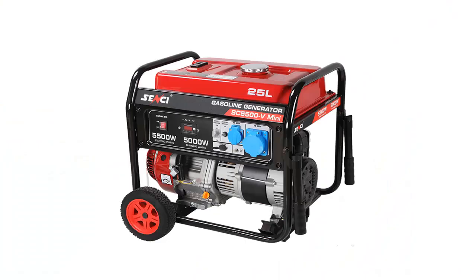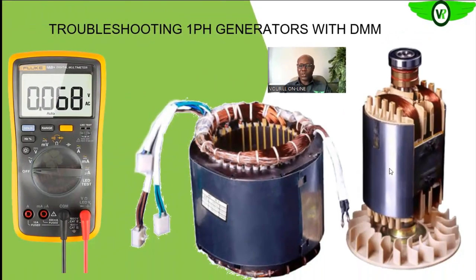So next, we are going to look at the single phase generator, okay? How to use the digital multimeter to troubleshoot your single phase generator. When you look at the single phase generator, it is somewhat different from what we have in the three-phase generator, but all the major parts are also present. This is the main field on the rotor, and this is the armature on the stator of the generator. Then we also have the exciter winding here.